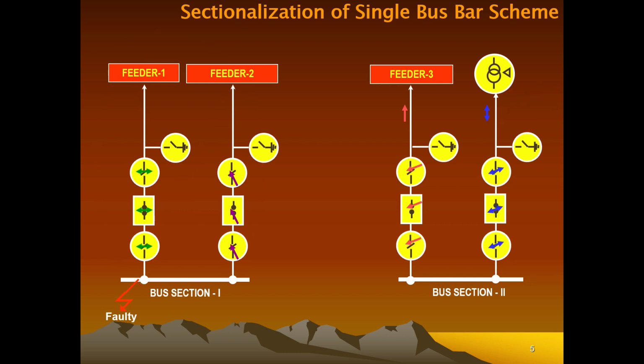And now the important thing is, how can you make a sectionalizer over here? Again, you can directly make a sectionalizer by connecting these two sections by one circuit breaker, and I have already explained in earlier sessions that you cannot have a circuit breaker connected between two live points, because in that case, in case of any maintenance work required on this circuit breaker, we cannot achieve it.